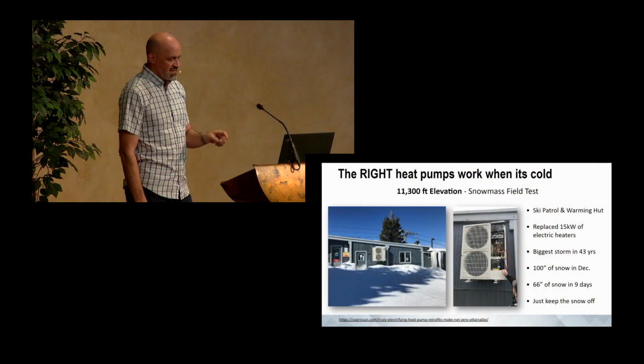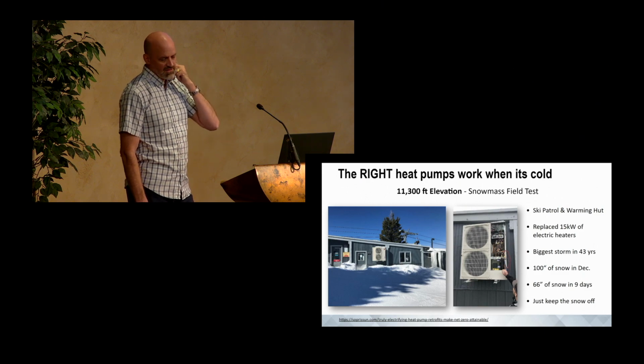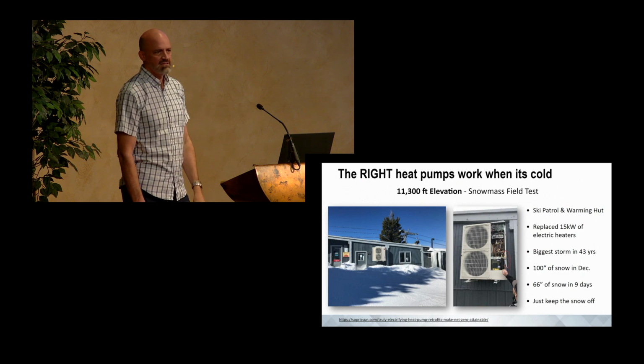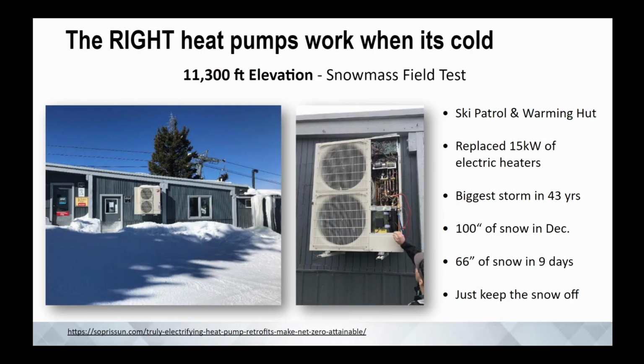This one is in Snowmass ski area, 11,000 foot, 11.3 elevation. People worry about elevation and how you do it up there. Well, you just do the math—you do the derate calculations to figure out, if we only get 90% of the capabilities at 5,000 feet, we're probably only going to get less than 80% at 10,000 or 11,000. That's oversimplifying, but you get the point.